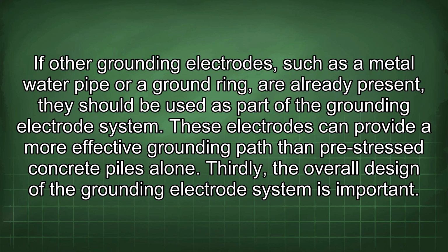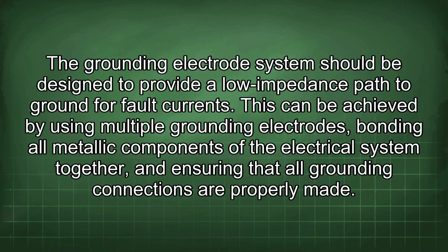These electrodes can provide a more effective grounding path than pre-stressed concrete piles alone. Thirdly, the overall design of the grounding electrode system is important. The grounding electrode system should be designed to provide a low impedance path to ground for fault currents. This can be achieved by using multiple grounding electrodes, bonding all metallic components of the electrical system together, and ensuring that all grounding connections are properly made.